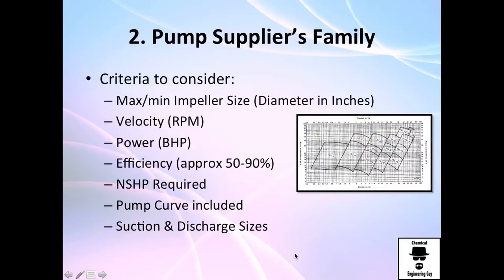What do we need to consider? The maximum and minimum impeller size, the velocity at which the pump can operate with typical values from 1750 to 3500, the power requirements, the efficiency including normal and best efficiencies, and NPSH requirements.